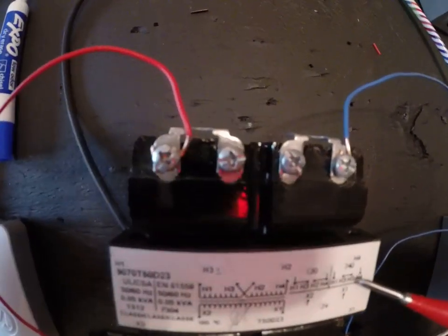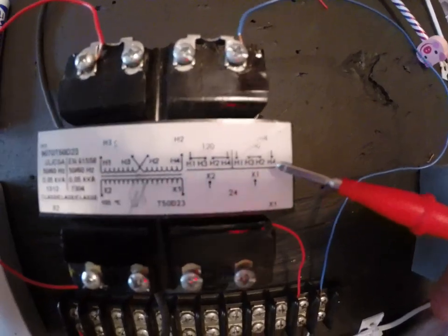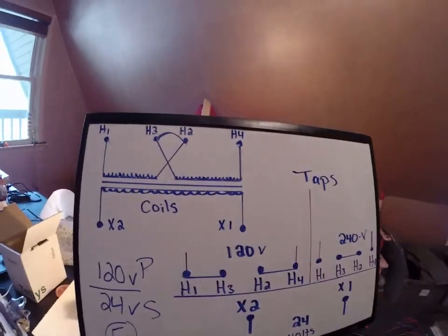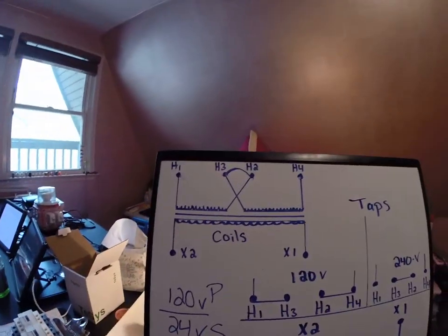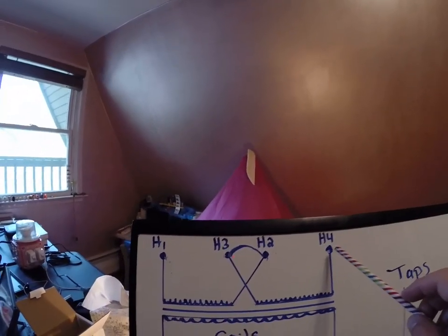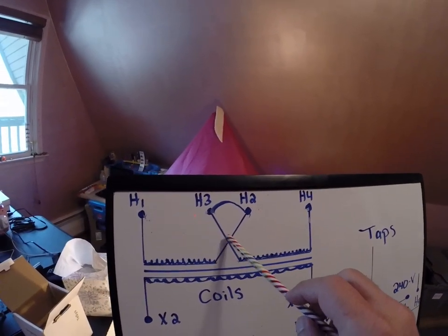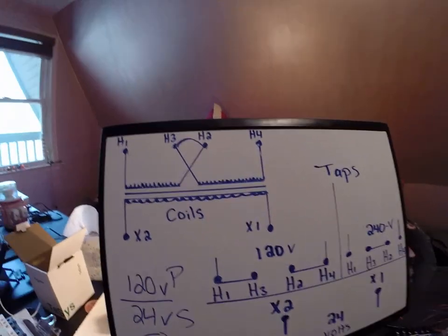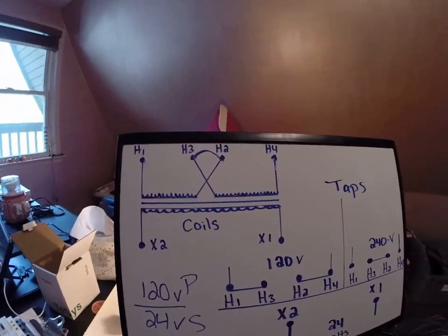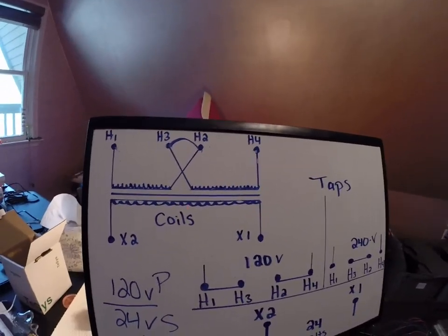I would just move the jumper from one screw to the other. And what I did is I put the jumper between two and three just to let you see that if I was to wire it for 240, that's kind of what this is looking like. So if I put this down for a second, you'll see that now by doing that, I've just connected these in series with each other. So if I went from here, I went through this coil, jumped across to pick up this coil, and now those are in series.